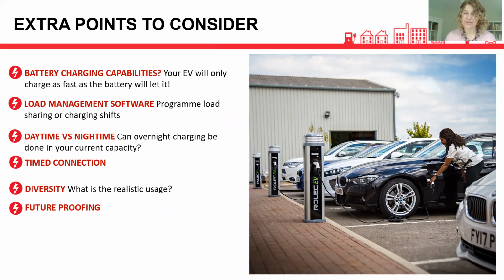So if you've got a 22 kilowatt AC charger, and your battery can only charge at 6 kilowatts AC, it's only ever going to pull 6. It's never going to pull that 22. So suddenly, your 22 kilowatt charger, where you've allowed 22 for each socket, might only be pulling 6 per socket. So that's 12 instead of the 44 that you needed.